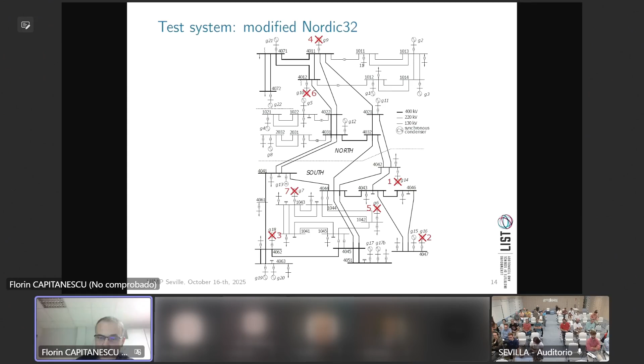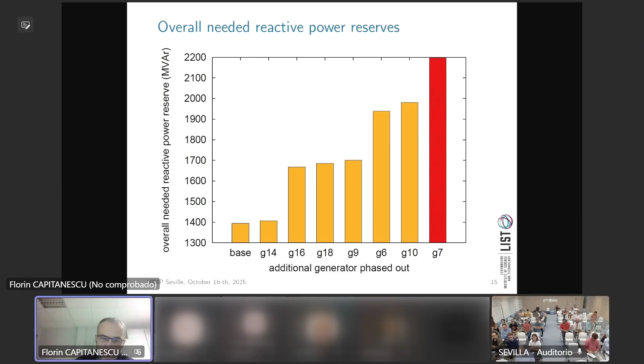So when I look into overall needed reactive power reserves, I represent here as a function of additional generators phased out. So in the base case, you see, I need only, let's say, 1.4 gigavar to maintain the system. Now, also you can criticize because in that case I simply add up megavars across the system, which obviously, if you add up megawatts, it's easier, but with megavars you need to be more careful. But okay, it's an assumption that you can criticize. Then I take one generator out, a second one, and so on until when I disconnect this G7, again, the problem becomes infeasible. You cannot control the voltages anymore properly within limits, okay?